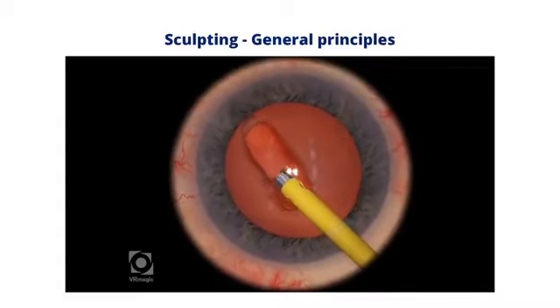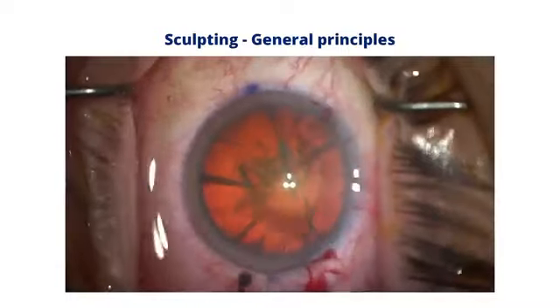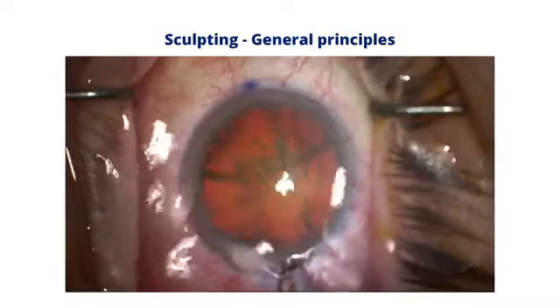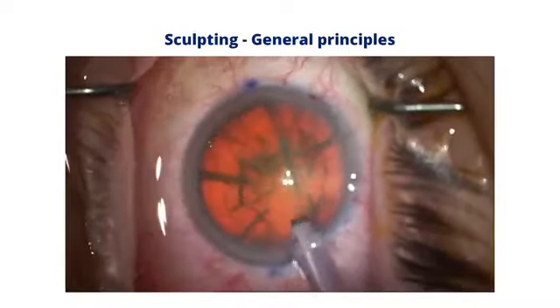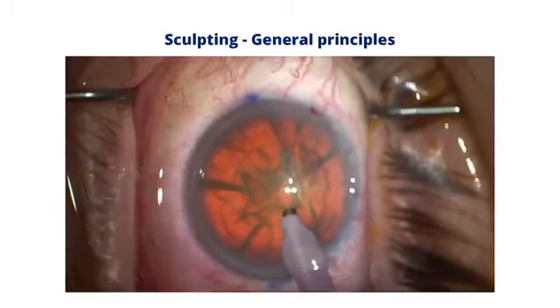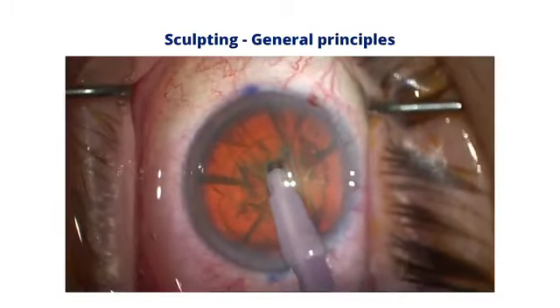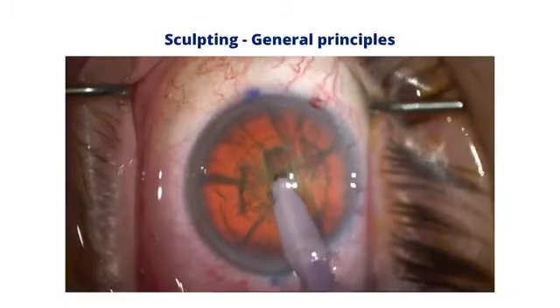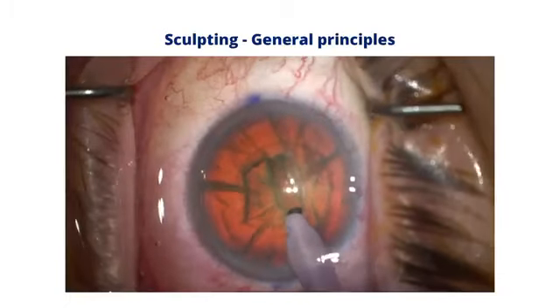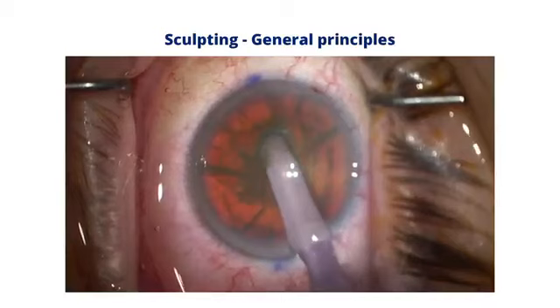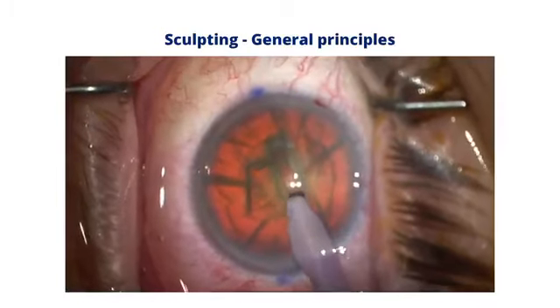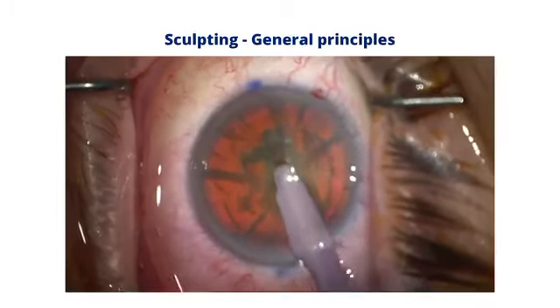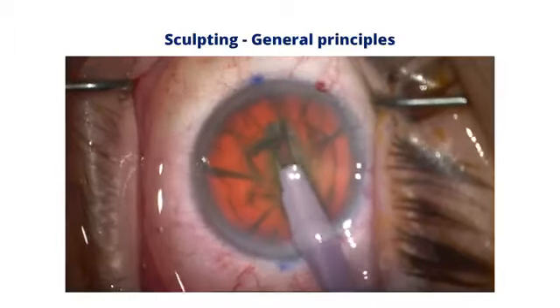Irrigation should be initiated before the phaco probe enters the eye. It should remain active for as long as the probe is in the eye. The irrigation level should be sufficient to maintain the anterior chamber depth. Use of the continuous irrigation setting might be useful for beginners. The nucleus should not move during sculpting. If the nucleus starts to move, the probe should be moved more slowly or the ultrasound power increased or the depth of the pass decreased.